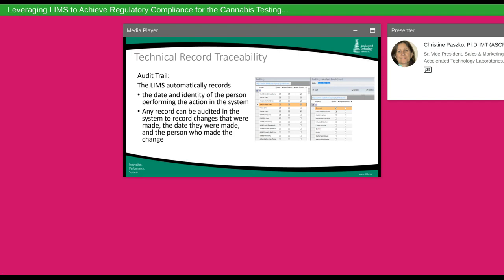Another process requirement is technical record traceability as it relates to the audit trail. If a result needs to be altered after it's been validated and approved, the system maintains the original result, date and time stamps, the person who entered the original result, and the units. After a change is made, it tracks the new result, date and time stamps, the person who made the change, and the reason for that change. This allows an auditor to run an audit report and see exactly what changes were made to final data and why.